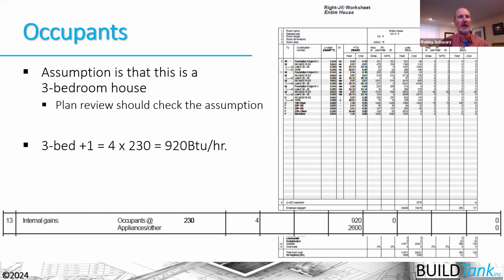And then you can see the appliances are also listed here at 2,600, and we'll get into the appliance here in a second. But this way you can just double check that they're not kind of manipulating the Manual J and that things are moving forward correctly here. 4 occupants, 920 BTU hours are taken into account for this 3-bedroom house. Remember, number of bedrooms plus 1 equal the occupants. We use that calculation when we're also calculating the ventilation needs of the house as well.